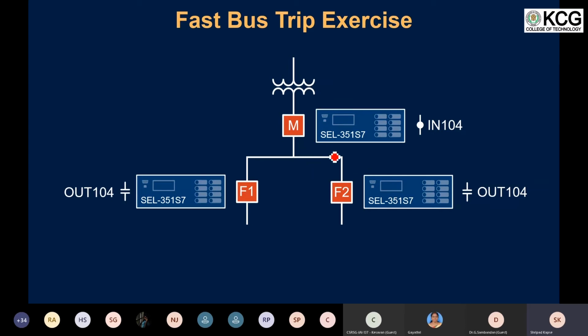So as a system of operation in the fast bus trip scheme, whenever the relay on the feeder is going to operate, we send a blocking command from one of the output contacts of the relay to the incomer relay, either on a communication protocol or on a hard wiring basis. And if the fault happens on the bus bar itself, then the relay on the incomer has a second level of overcurrent limit, which looks at a higher overcurrent setting.